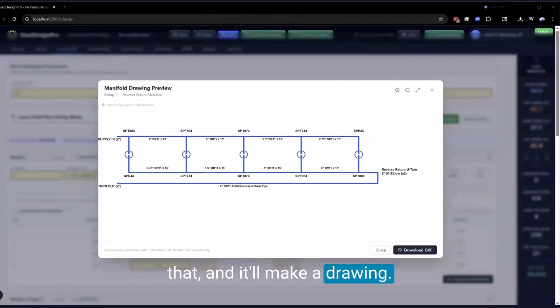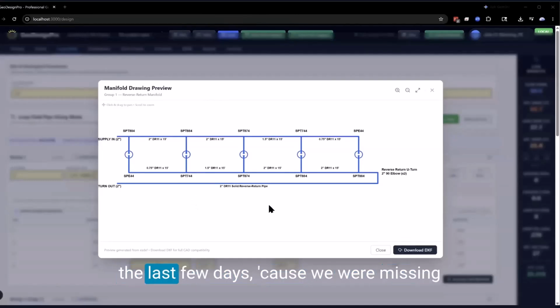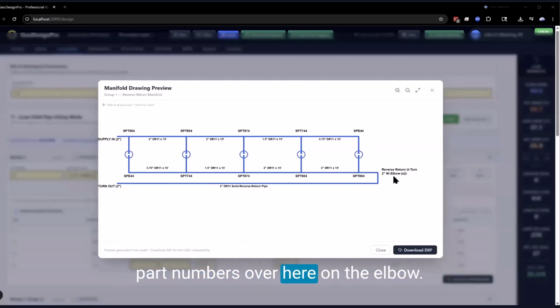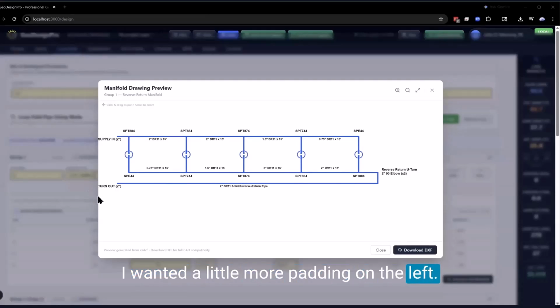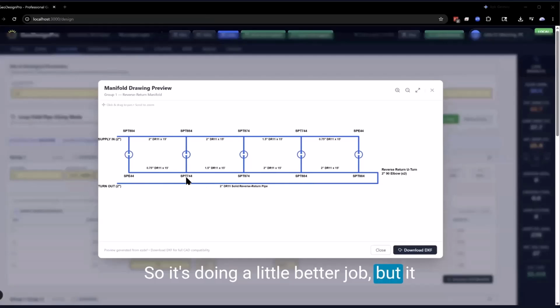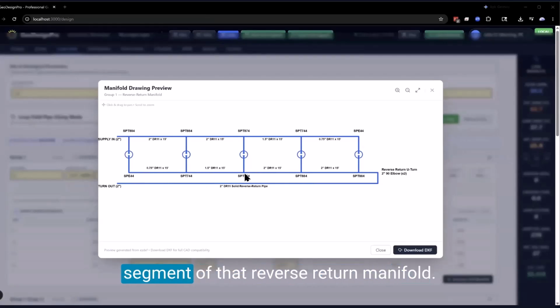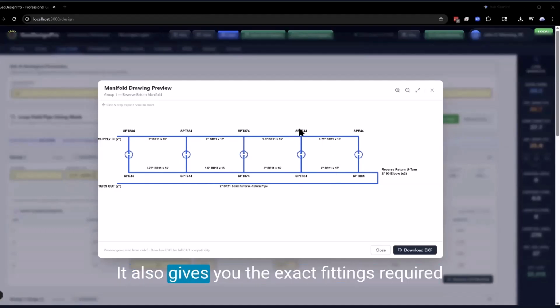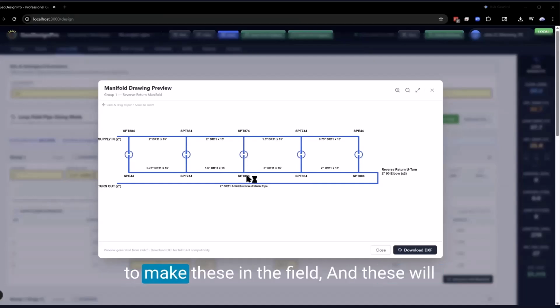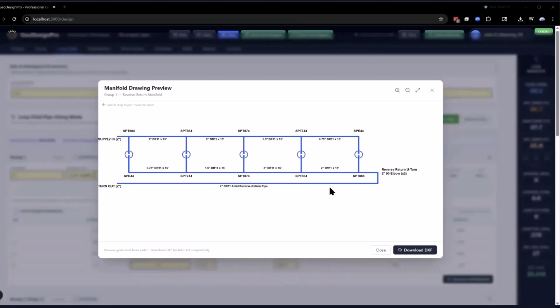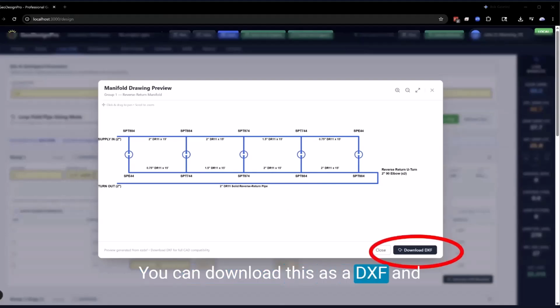One of the things I was really challenged to figure out how to do was generate the CAD drawing. Down on the lower right, you generate that, and it'll make a drawing. This has actually been improved just in the last few days because we were missing part numbers over here on the elbow. I wanted a little more padding on the left, so it's doing a better job. It basically tells you the diameter of each segment of that reverse return manifold. It also gives you the exact fittings required to make these in the field, and these will all roll forward into the bill of materials. This is a simple manifold. You can download this as a DXF and paste it into your own CAD drawings.